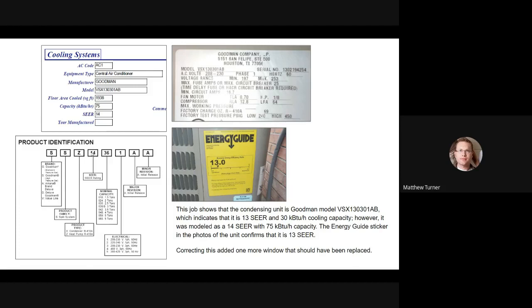The next two digits are the SEER rating, so from this model number, this is a 13 SEER. Then it looks like two more digits, but as you go down the table, it's actually the next three digits that tell us the capacity. That's the 030. So we can see the capacity, 030, is 2.5 tons, exactly what Kyle was guessing. The 030 represents the kBTUs, 30,000 BTUs.